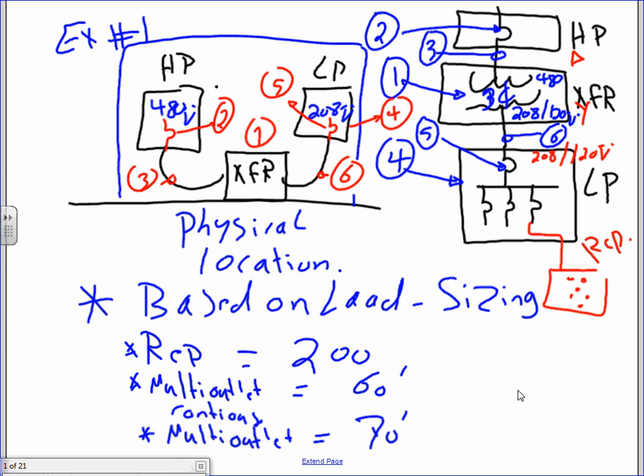And we also, Derek, do you remember the 208/120 bus duct for that industrial building that we have? How are you going to feed a 208/120 bus duct? Well, guess what? You have to do the same thing. So we're going to have a feeder from the main panel feed a transformer that takes the voltage from 480 into 208/120. Instead of dumping the voltage into a panel, we will be dumping it into a 208/120 bus duct. Cool? So that's how physically it looks. Now, as a one-line diagram, guys, that's how it looks in one diagram.